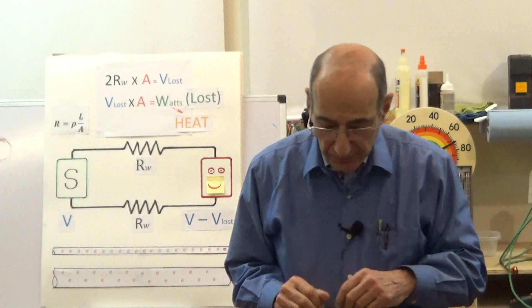Heating appliances use a lot of power. They don't necessarily use a lot of energy throughout the year - you don't toast all day long, it's for a short time that you make toast. But while you're making it, you're probably drawing 7 or 8 amps. Coffee pots don't use a lot of power throughout the year either, but when they're percolating, they're probably using 7 to 8 amps. So we're already at 14 or 15. Now you throw in a microwave at 8, 9, or 10 amps, and we're way over 20.